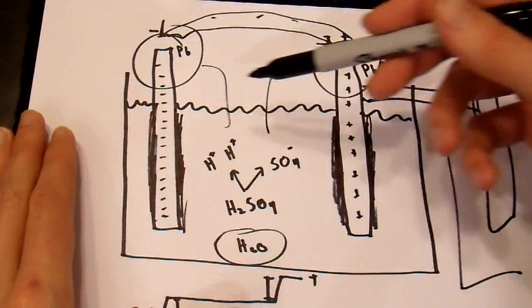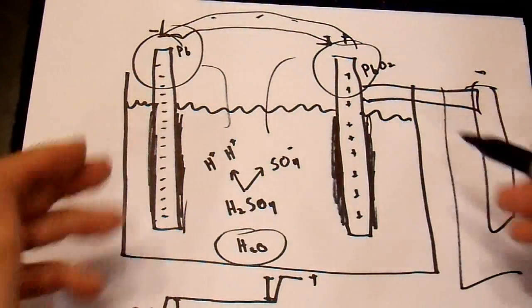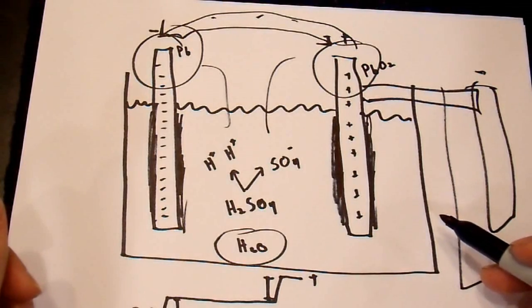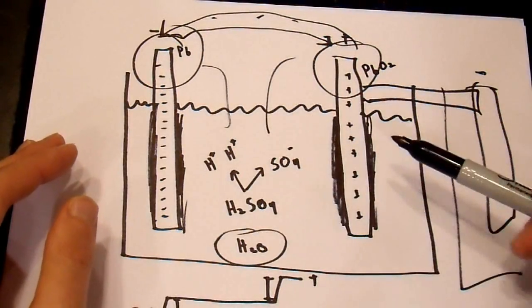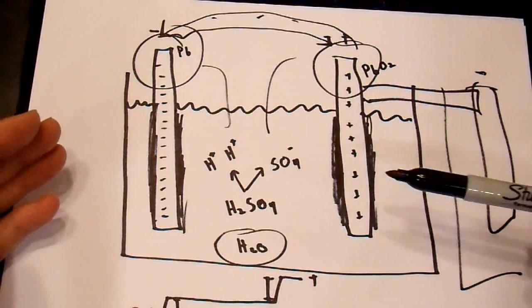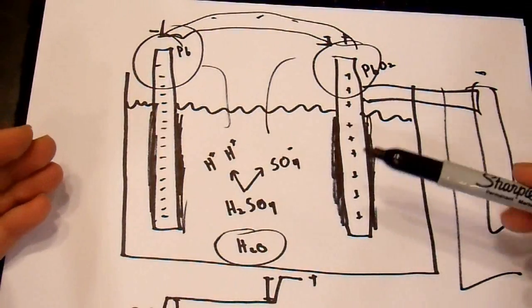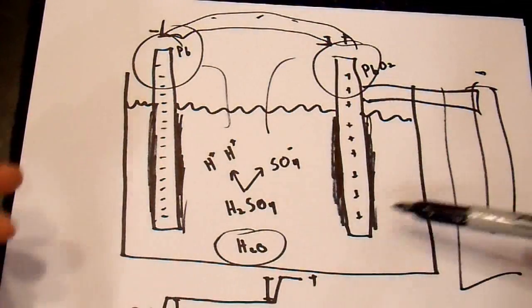For example, if you have a lead antimony battery in particular, their efficiency is lower than a lead calcium battery. And, part of the reason for that is because they outgas. You have electrolysis at the terminals here. And, the battery acid actually splits into hydrogen and oxygen. And, some of that escapes.